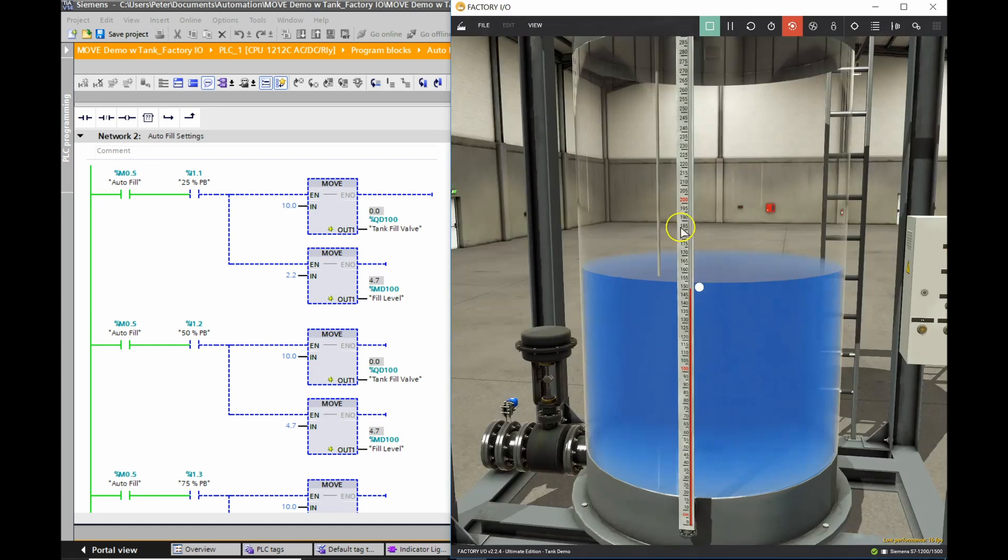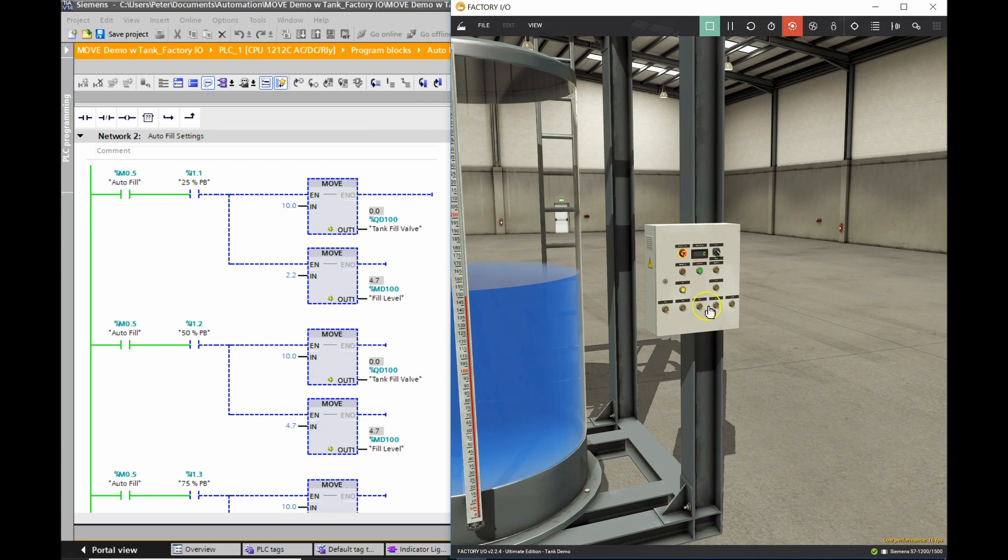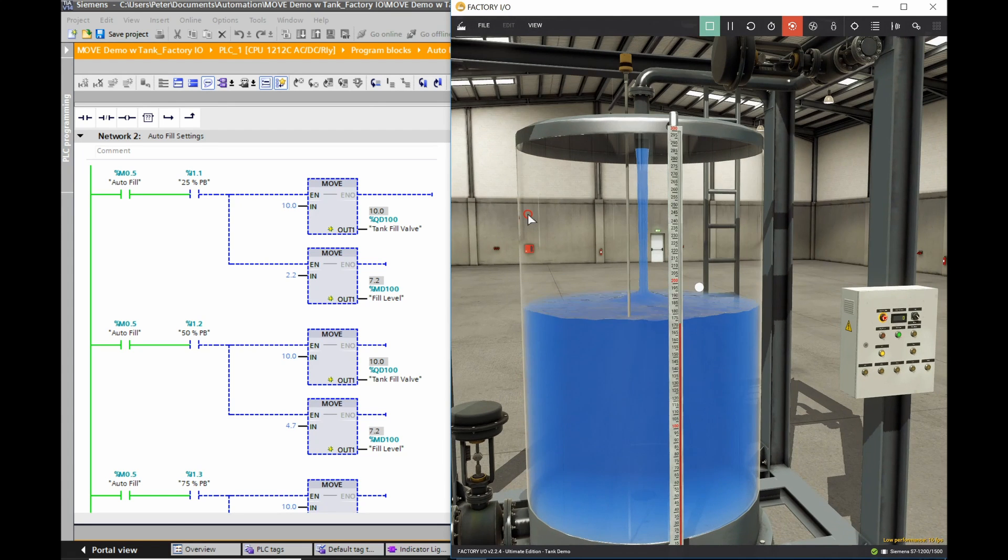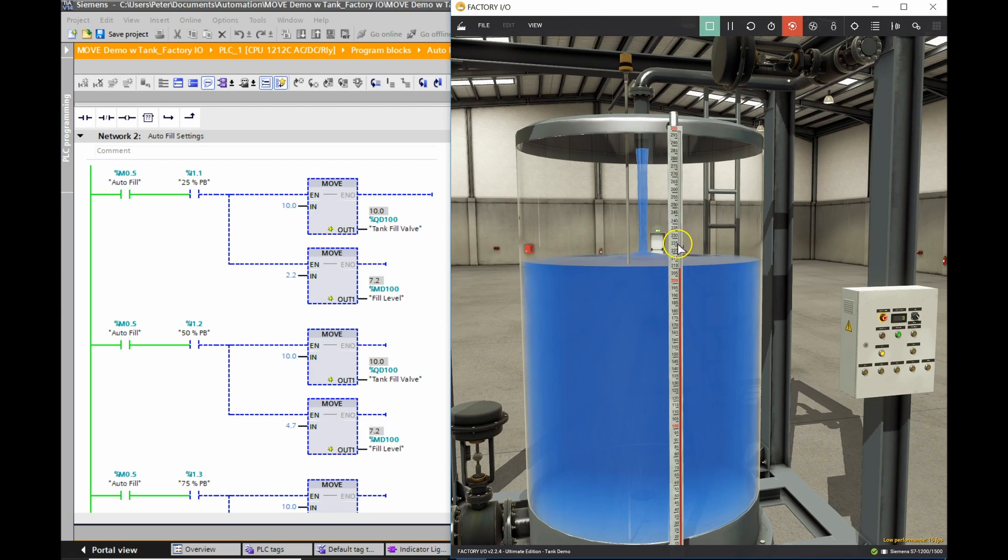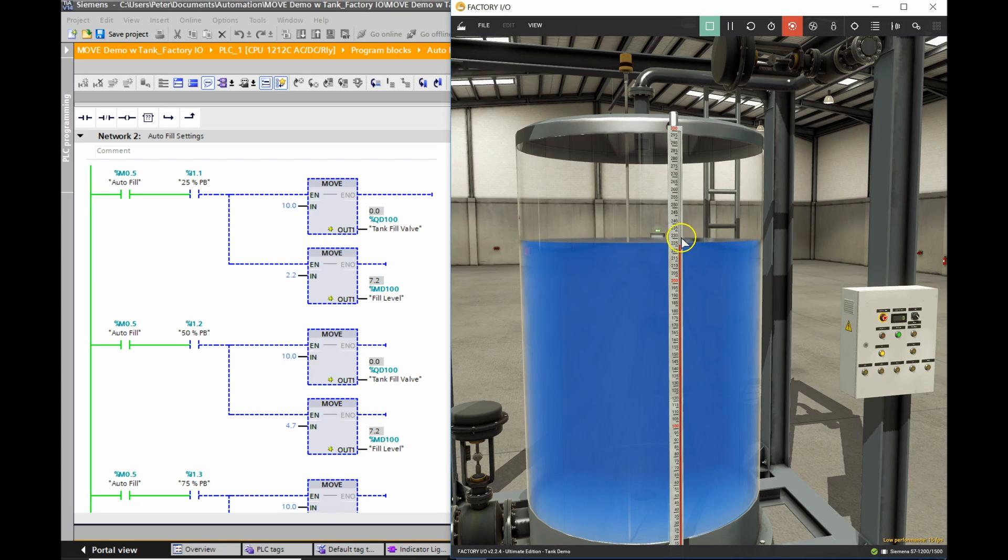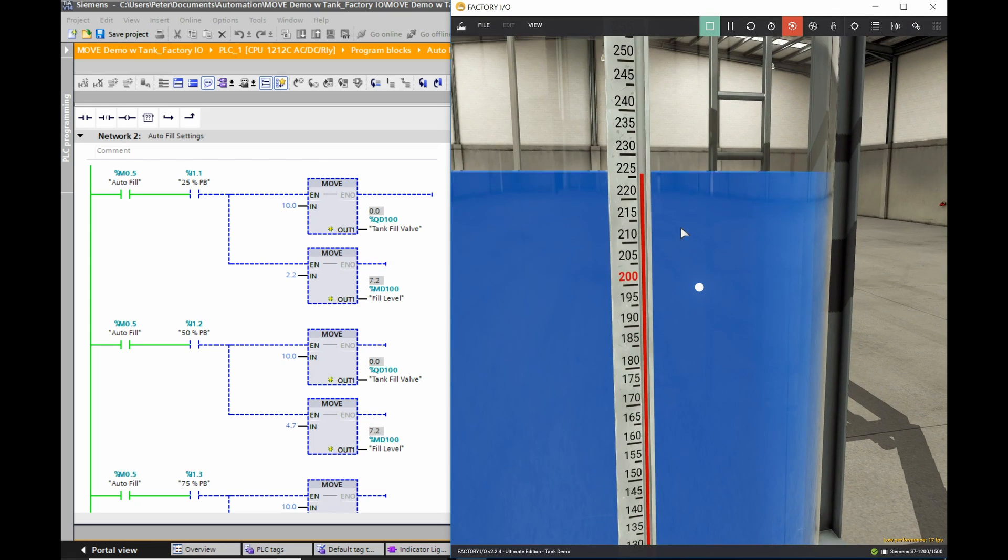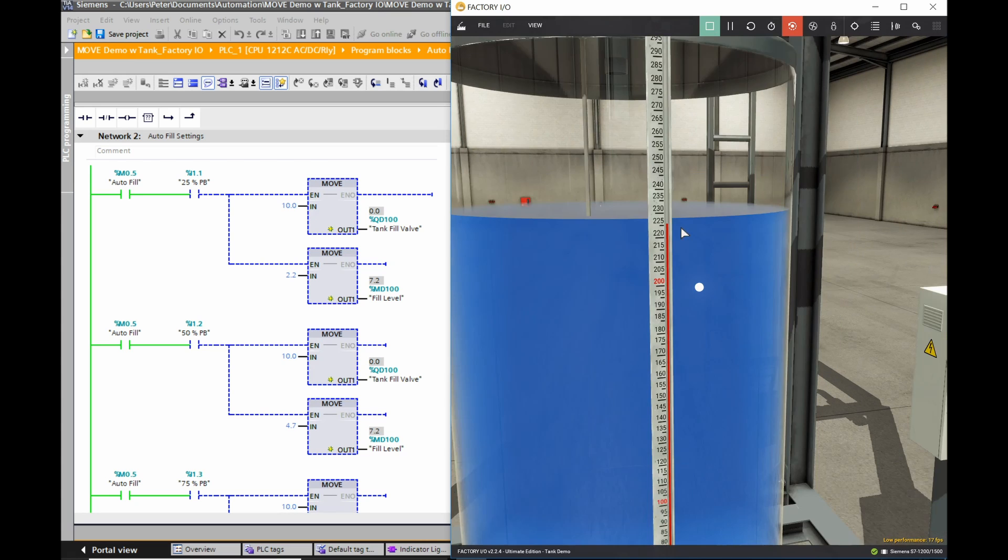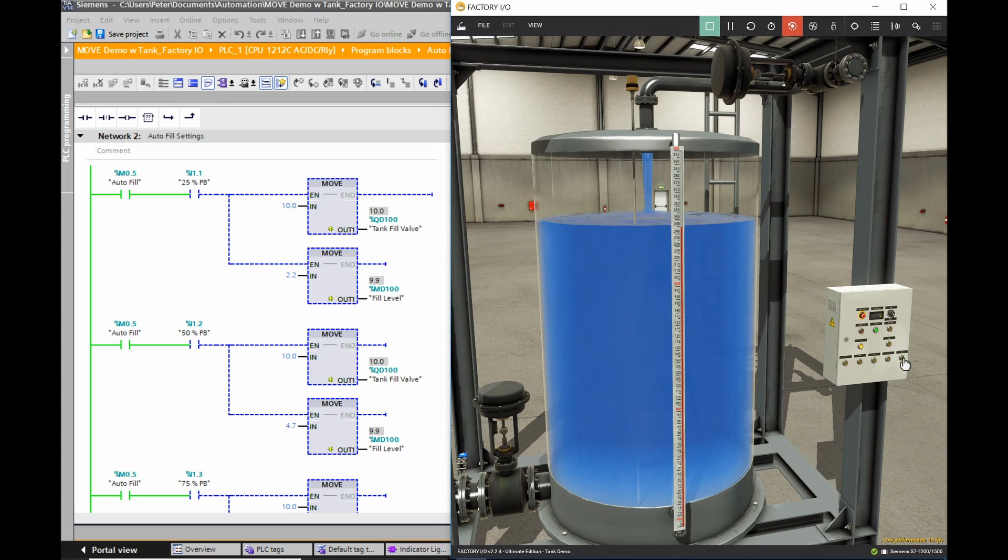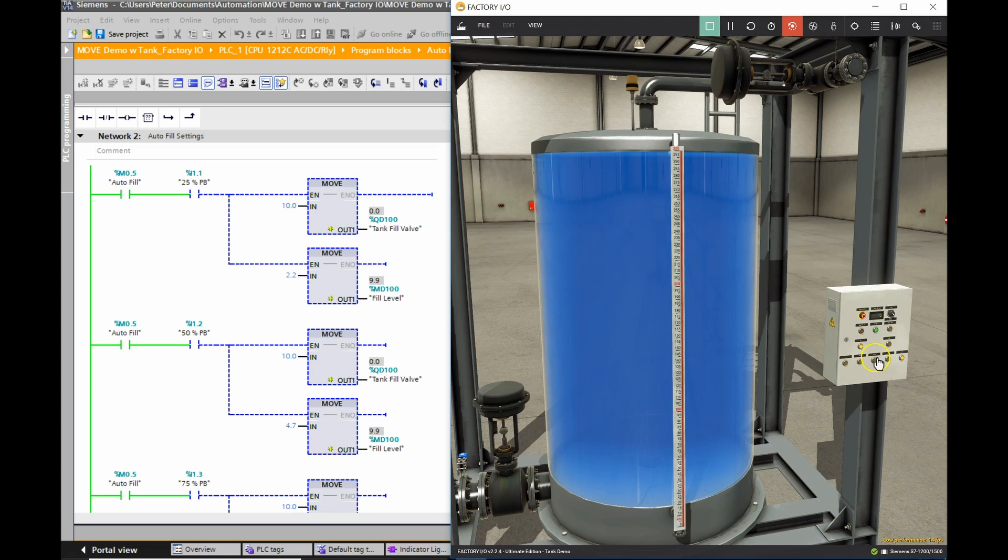Let's go to 75. Sometimes things do not work out, even though you've tried very hard for them to work out. So let's go to 75 now. 75 is 225. So at 225, we should stop right about here. Beautiful. And hopefully this indicator light turns on. So obviously I need to work on the range in which those indicator lights are turning on, because we are basically dead on, or maybe I'm just a little bit shy of that 225. That's pretty good. So I'll have to work on those indicator lights. We're going to 100%. That goes to 300 and should stop. Nice. And that indicator light for 100% kicks in there. So it looks like I need to work on my 50 and my 75% there.